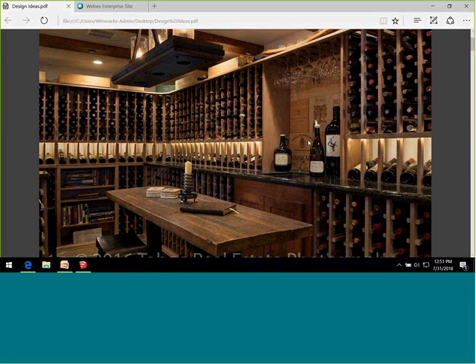If we're using glass, whether in the door, side lights, or entire glass walls, we need to understand that puts an excessive heat load on the room. So when we use glass for that room, it's the highest R-value grade we can achieve, exterior grade glass, and we factor that into properly calculating the right cooling unit. This wasn't seen as often 15 years ago—rooms that are almost entirely glass walls.